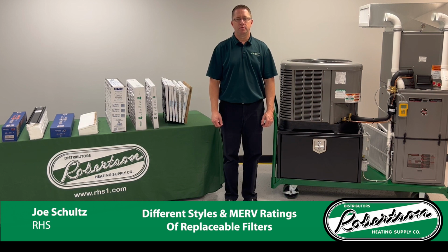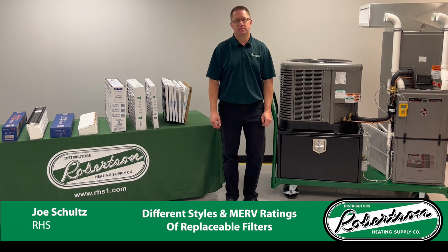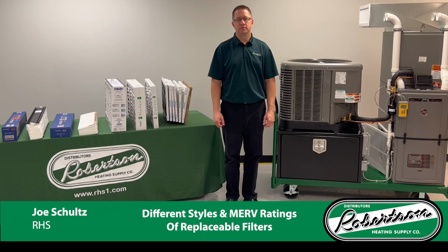Merv ratings of 5 through 8 filter down to particle sizes 3 through 10 microns, which includes everything I mentioned prior, plus mold, spores, cement dust. Applications include residential, commercial, paint booths.